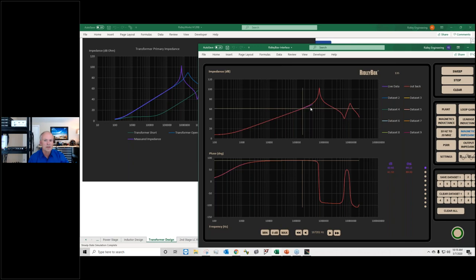And now you start seeing the two deviating from each other. You can see our second transformer has a much better resonant frequency on it. Much happier with that one. But it's still got this resonant dip. The dip has moved from 5.5 megahertz out to 13 megahertz in this case, but it's still going to ring at that frequency.